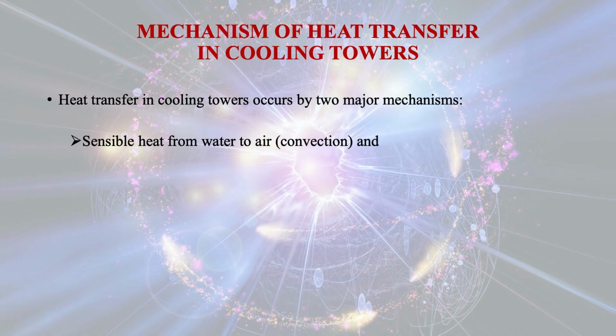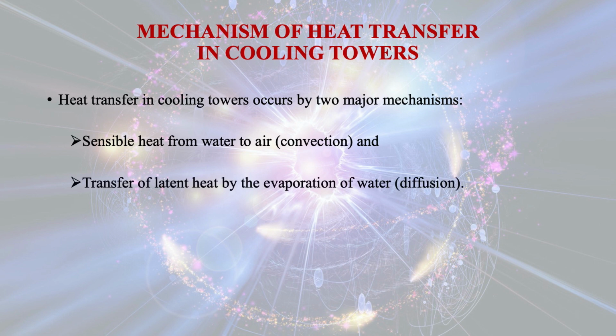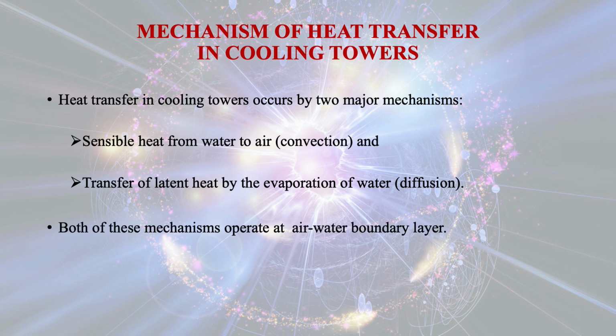So the two major mechanisms are: sensible heat from water to air, that is convection, and transfer of latent heat by the evaporation of water, that is diffusion. Both of these mechanisms operate at the air-water boundary layer.